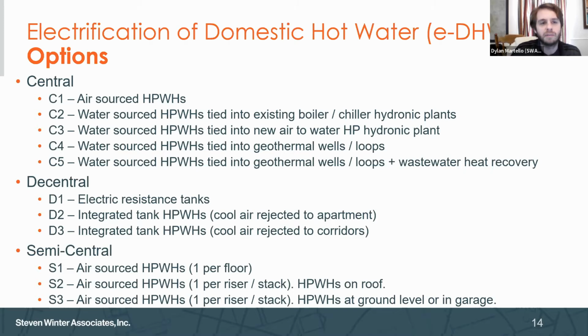Lastly, there are some semi-centralized approaches where you could do one air source heat pump water heater per floor, or per riser or per stack, locating the heat pump water heaters on the roof. Or if you have a below-grade or ground-level parking garage, you could utilize space there, potentially doing an air source heat pump water heater per riser per stack, with the water heaters located at the base of the building. So these are some different approaches and options for electrifying our domestic hot water.